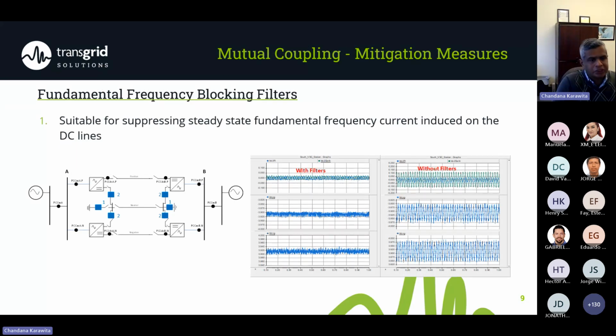So let's talk about some mitigation measures. For the mutual coupling, for the AC currents appearing on the HVDC, we need to somehow suppress these AC currents. The easiest way is to add blocking filters. We can have fundamental frequency blocking filters added like this. Usually we add the filters at the neutral, close to the neutral bus, because of the low voltages and the cost is low. And usually we need 3 of them for each pole and the ground connection as well, if there is a ground connection, and similar at the other end as well. And you can see the impact with and without filters. So if you design the filters properly, you can suppress the AC current significantly.